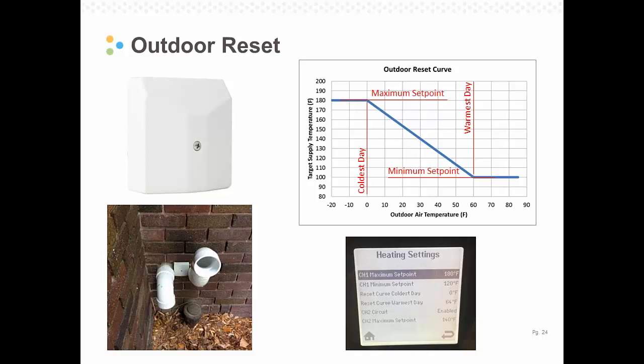One of the key parameters to the outdoor reset is making sure that you actually know what the outdoor air temperature is. So it's important to look at the install requirements for that sensor. You can see in the lower left-hand corner, this is maybe a non-ideal application of a sensor, where you're likely to see some influence from the exhaust right next to the sensor. Typically there's some information in the manual, but you want to make sure you're getting a good reading of the outdoor air temperature, thinking about things like exhaust, sunlight, snow accumulation, those sorts of things.